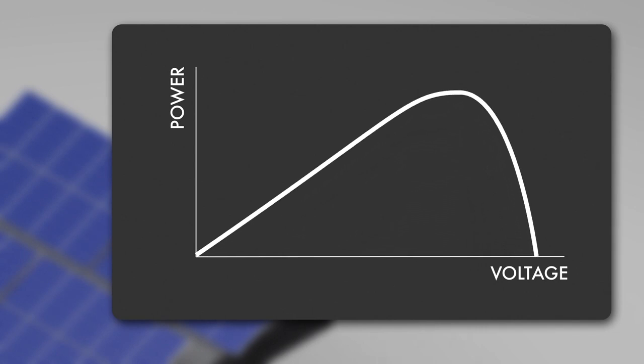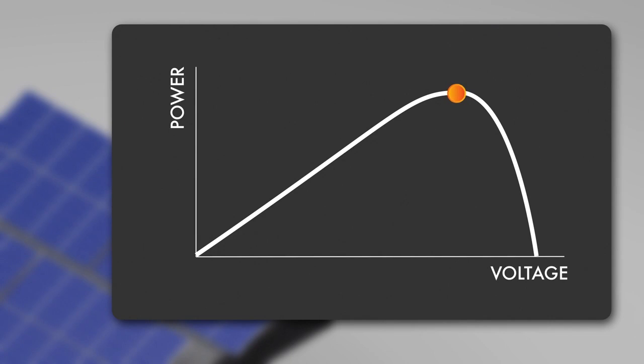There is an optimum operating point detected by an MPP tracker within each solar inverter extracting the maximum power of the PV array. This maximum point on the power curve is called maximum powerpoint, or MPP, and the correspondent voltage is called MPP voltage.